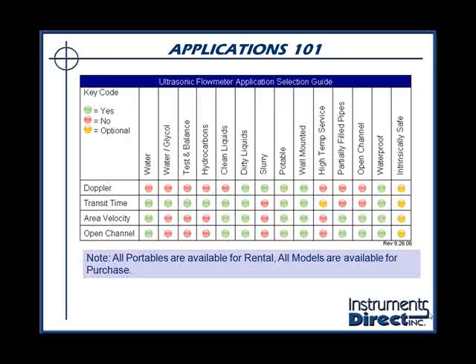Here's a brief look at traditional applications used for ultrasonic flow meters. Again, as you can see, an ultrasonic transit time flow meter works in an aqueous base application, whether it's water or oil, it really doesn't make any difference, or mixtures of them. The Doppler technology, again, is used for heavier slurry applications.